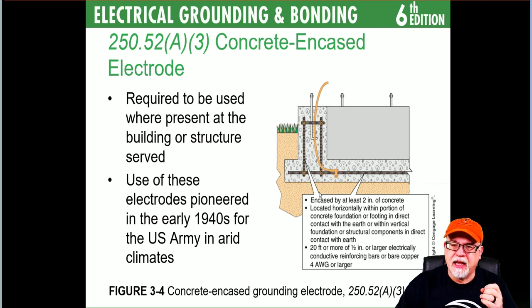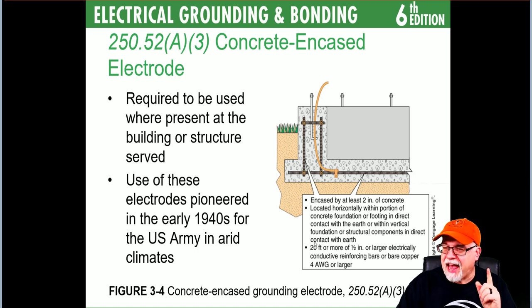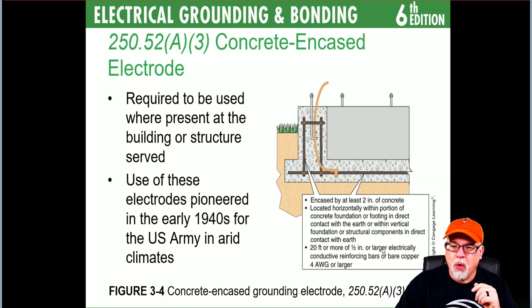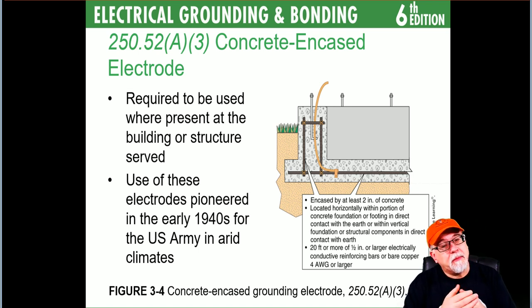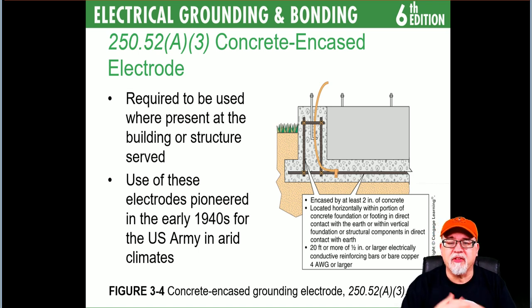As shown in the graphic, the rebar has to be encased in at least two inches of concrete, located horizontally or vertically within the foundation or footing in direct contact with the earth. It has to be 20 feet or more of half-inch or larger electrically conductive reinforcing bars, or bare copper of AWG 4 or larger. Tying pieces together requires only typical tie wires — nothing special, no special clamps.